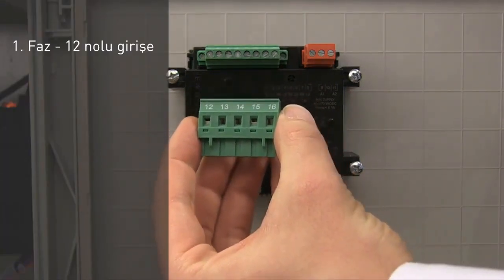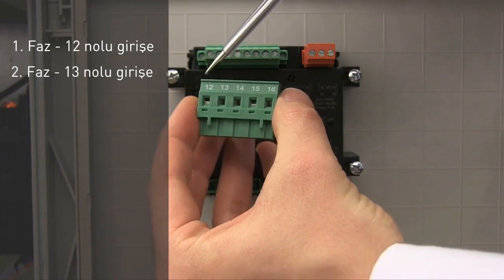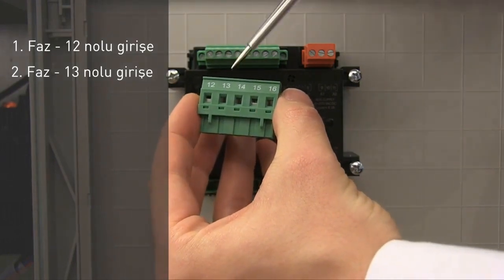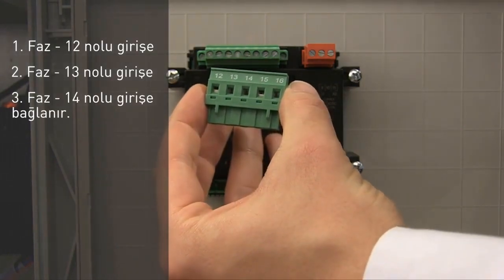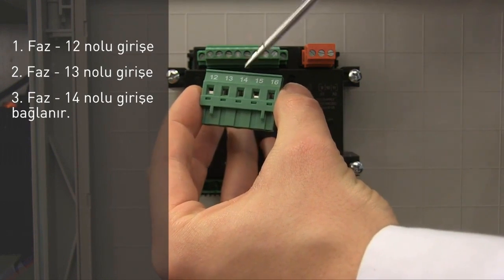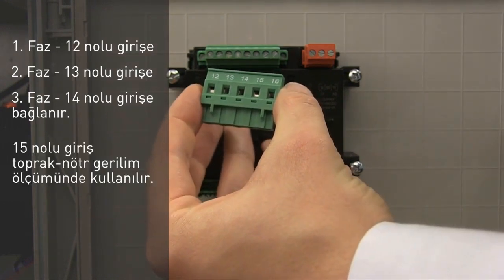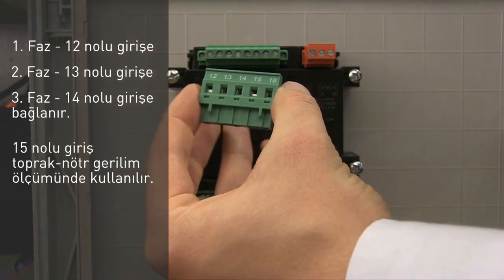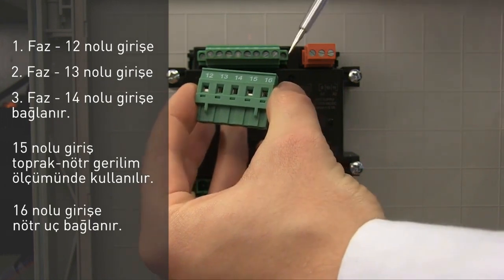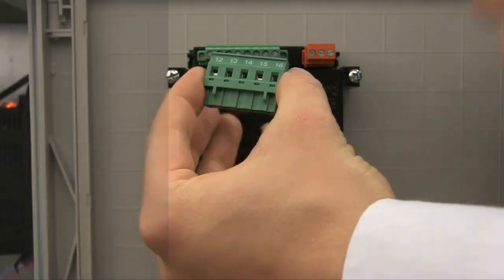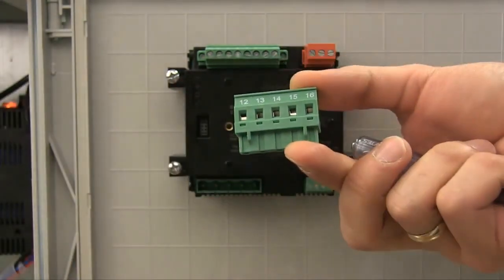The voltage lead from the first phase goes to input number 12. The voltage lead from the second phase goes to input number 13. We also connect the voltage lead from the third phase to input number 14. Input number 15 is used for measuring ground neutral voltage. We connect the neutral lead to input number 16.